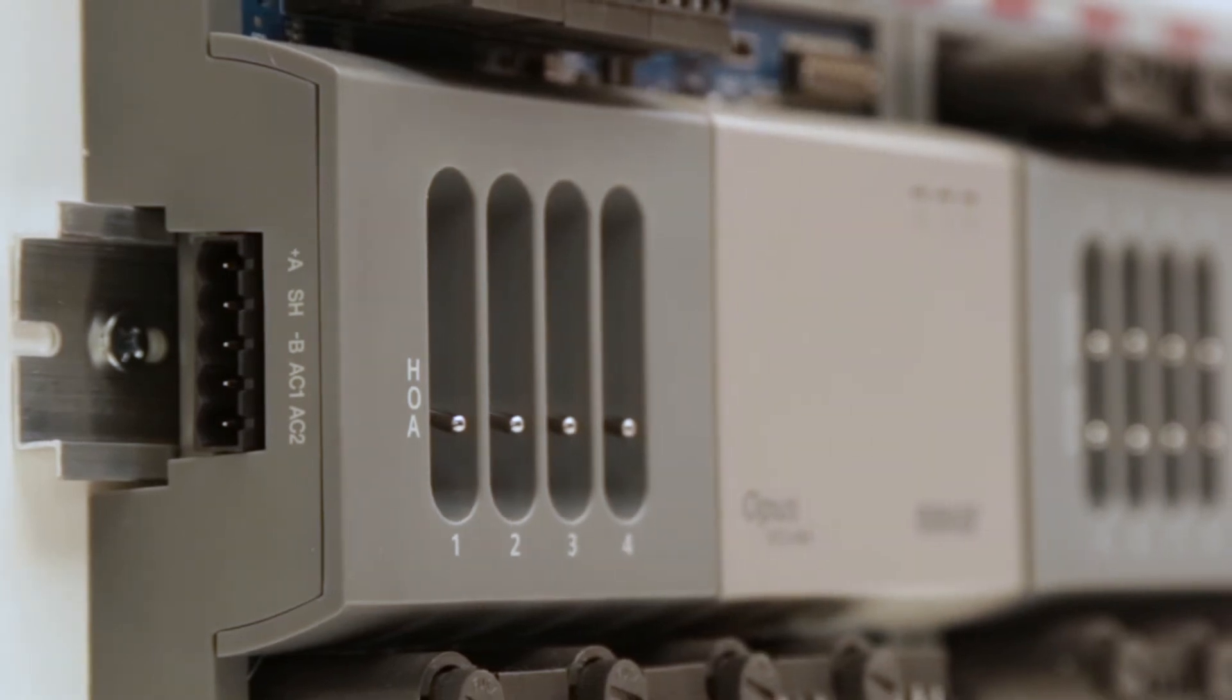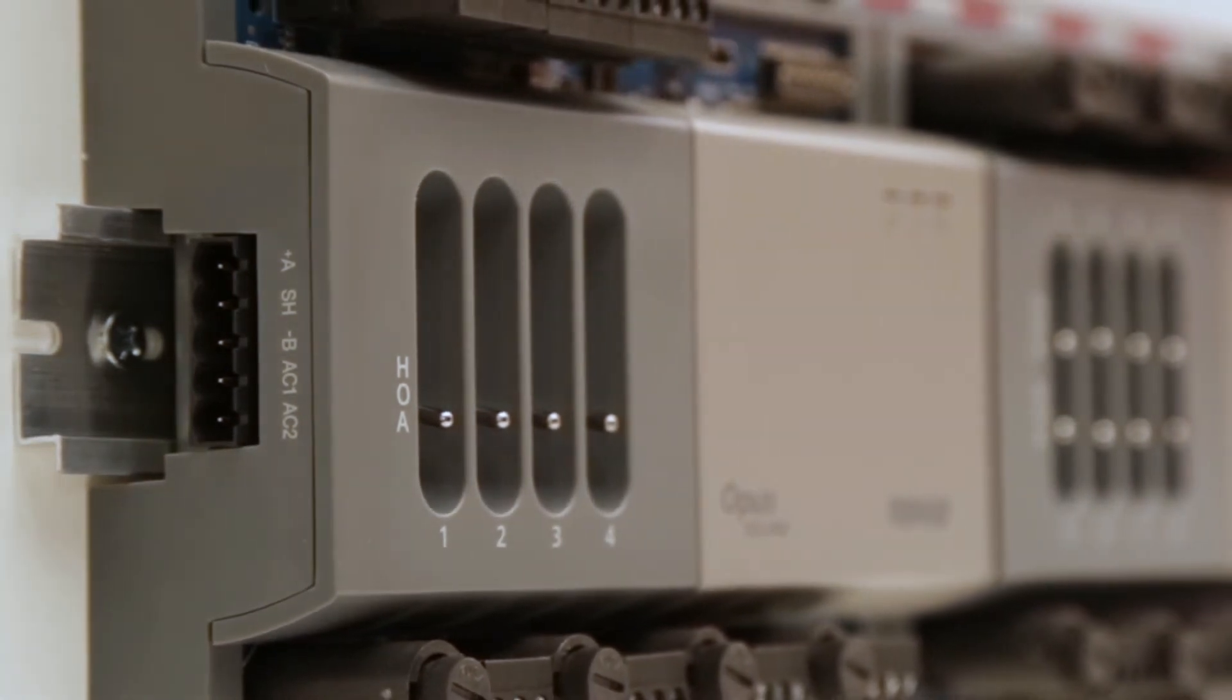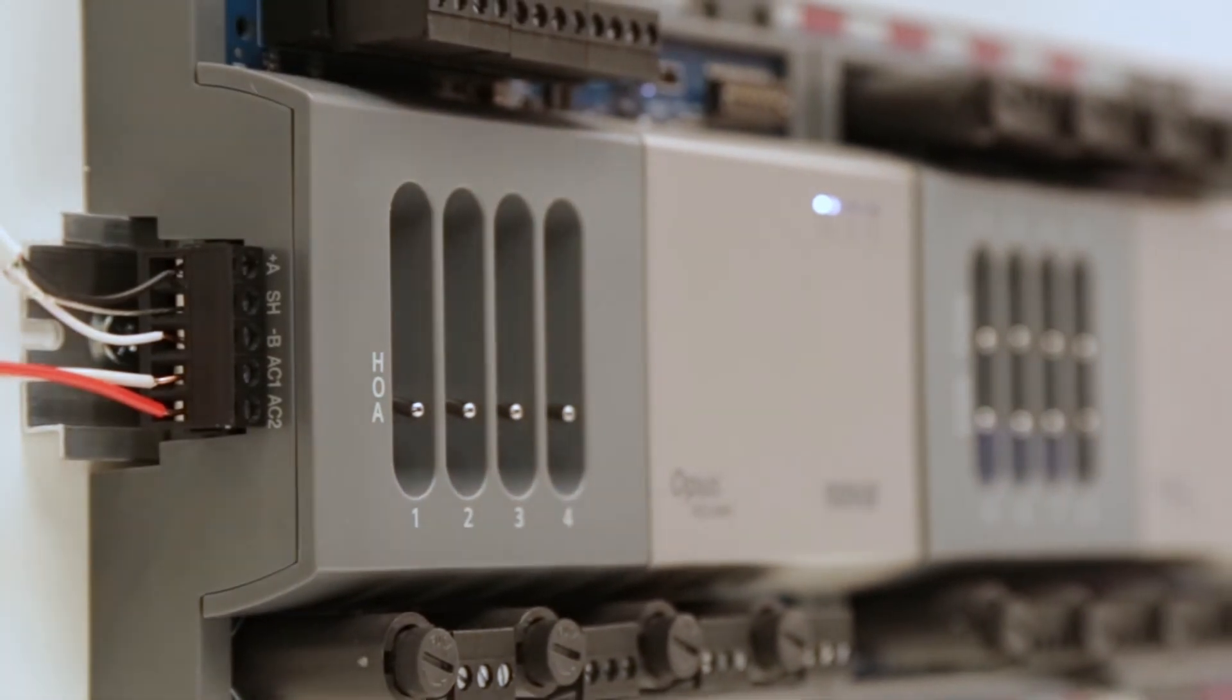Regarding power, a 24 volt AC transformer should be used per XIO series and should not exceed 100 VA.